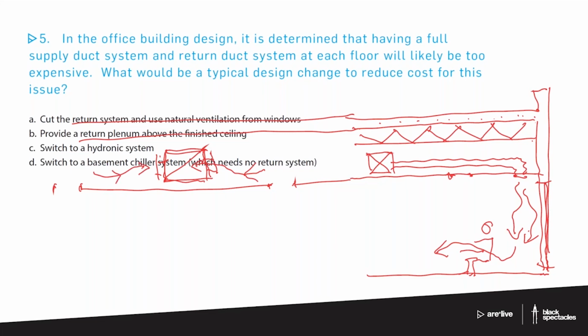That negative air space is going to pull air through these holes—they don't look like holes, they look like registers—drawing air up from that space all over. This lets us do the system without a full second return system; we just need enough of it that air can find its way up into that interstitial space. So at my desk, some of that air, from the vacuum created, enters and flows over and around the duct, up into the structure space, flowing around up there and finding that negative need at the return duct.